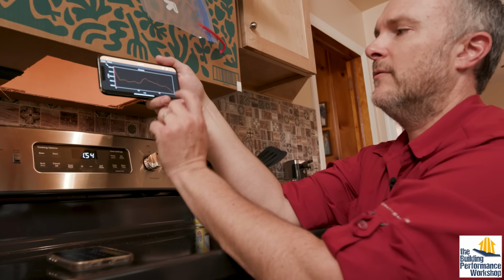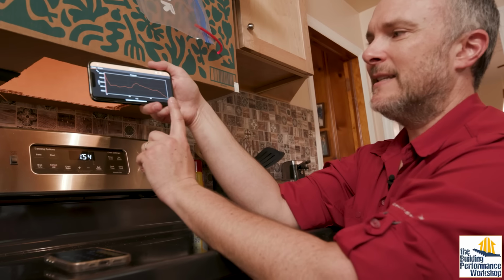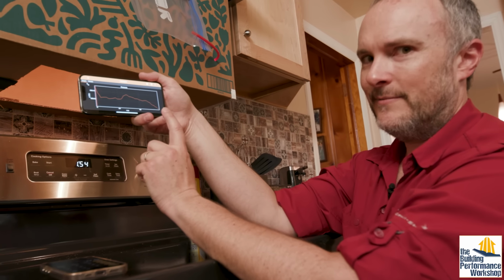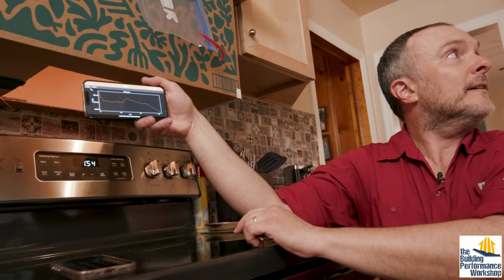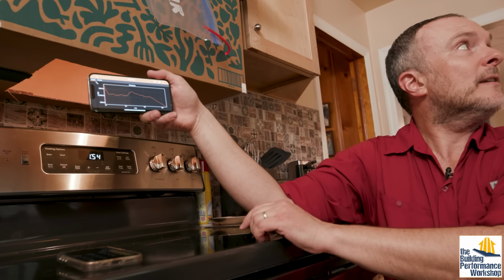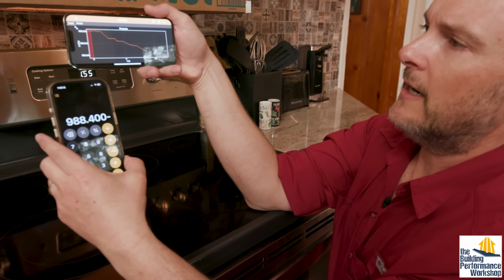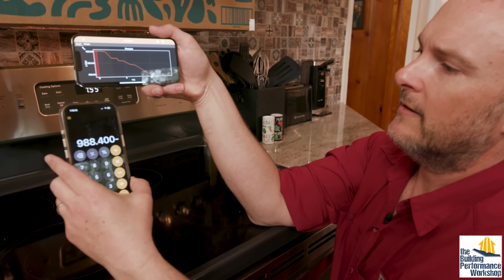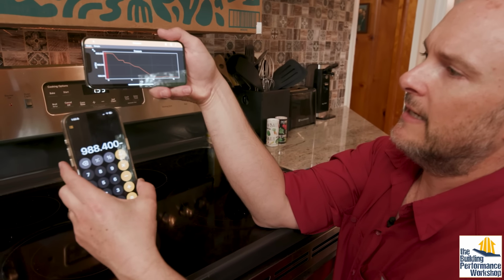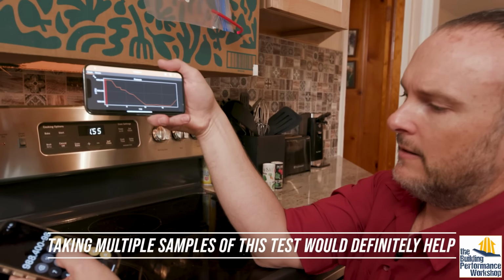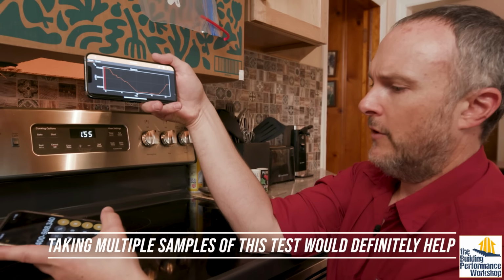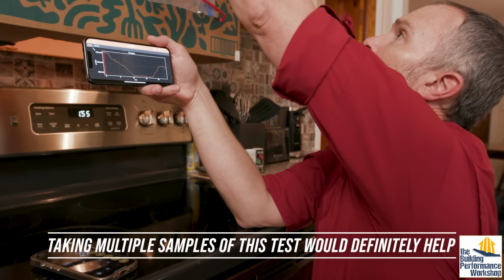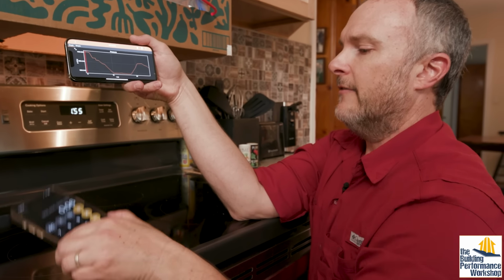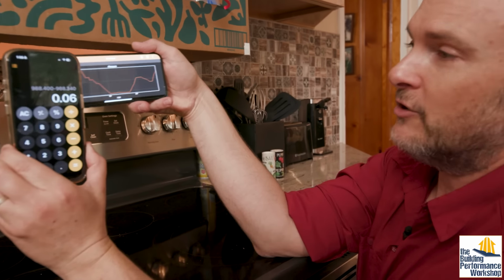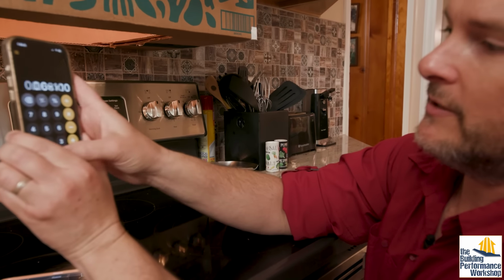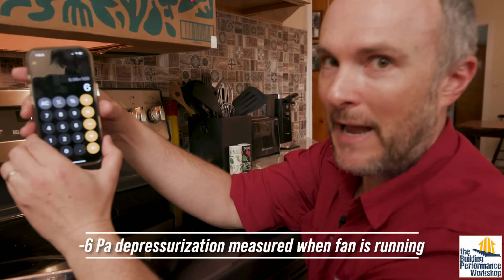Okay, so what we just found, see how messy this is? This is the weather doing that. So it's a little bit cloudy. There's a little bit of a breeze outside. So we started out at 988.400 and we're down to 988.340 with the fan on. Okay, and that is a difference of 0.06 hectopascals, which times 100 is 6 pascals.